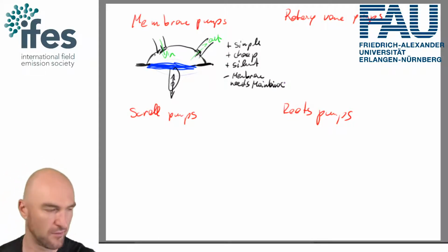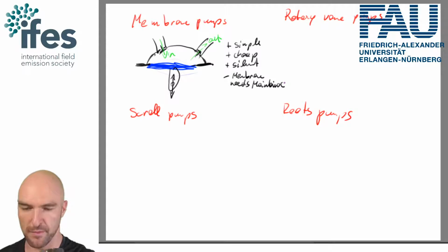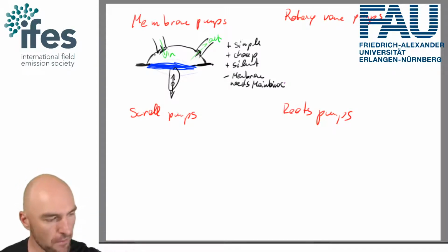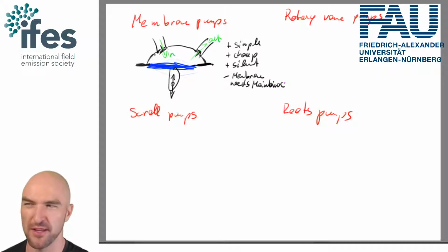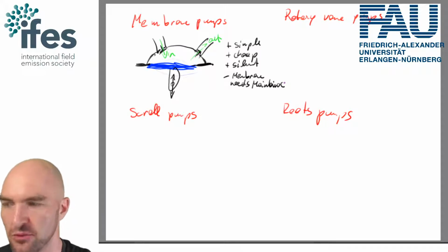And roughly, if you've operated a LEAP, they use membrane pumps. Then you will see that every 2 years or so you'll get the membrane ripping, and then you need to replace the membrane. And here the ultimate pressure that you can get to is around 1 millibar. I should write that in a way that's a bit easier to read. P is around 1 millibar. Okay.